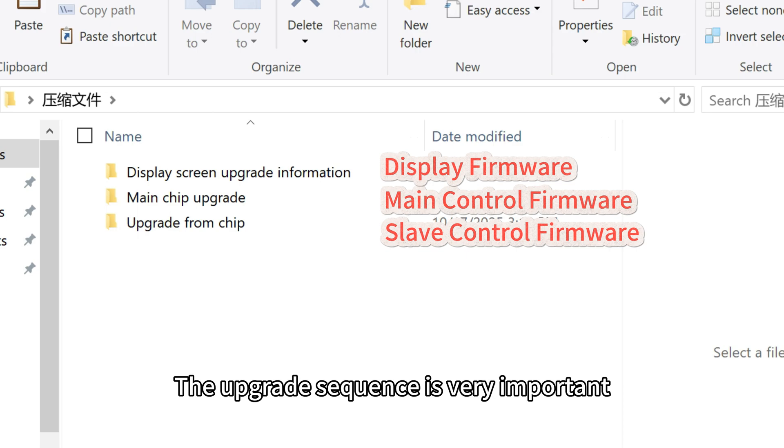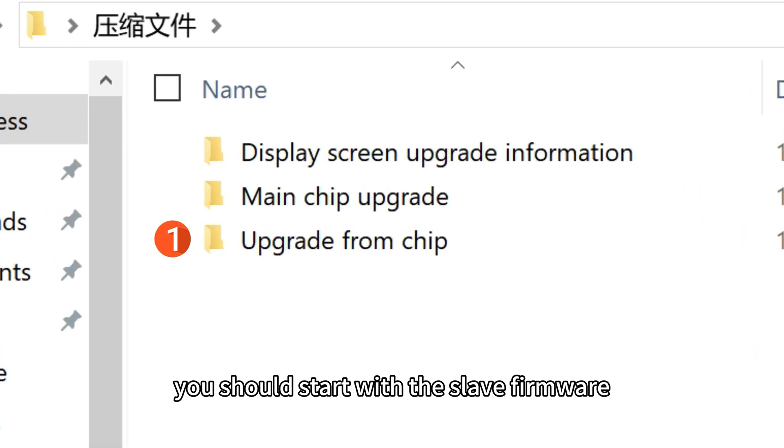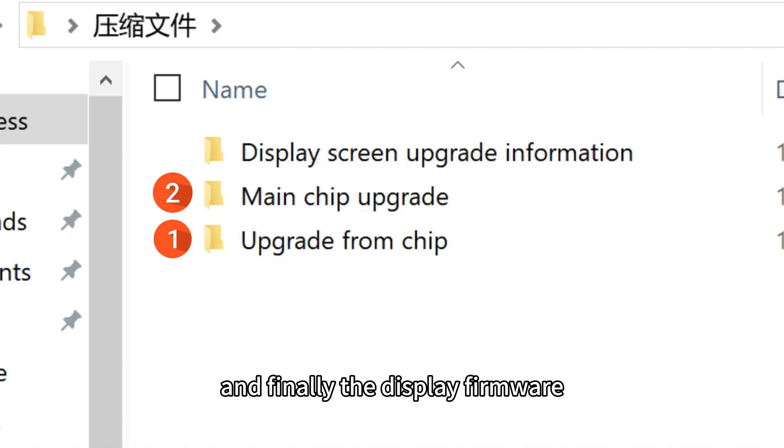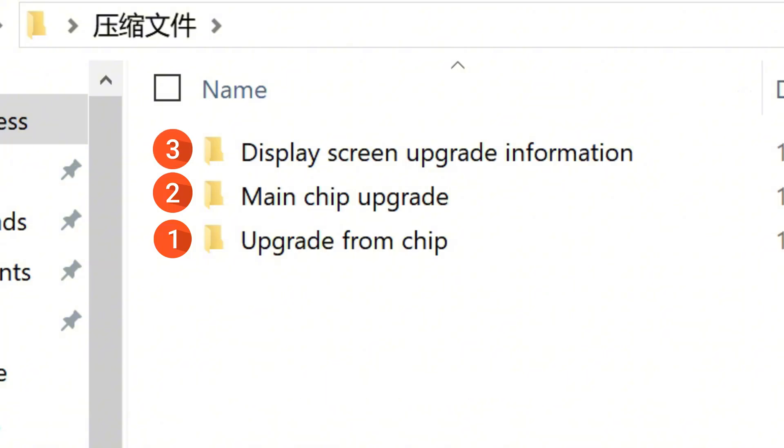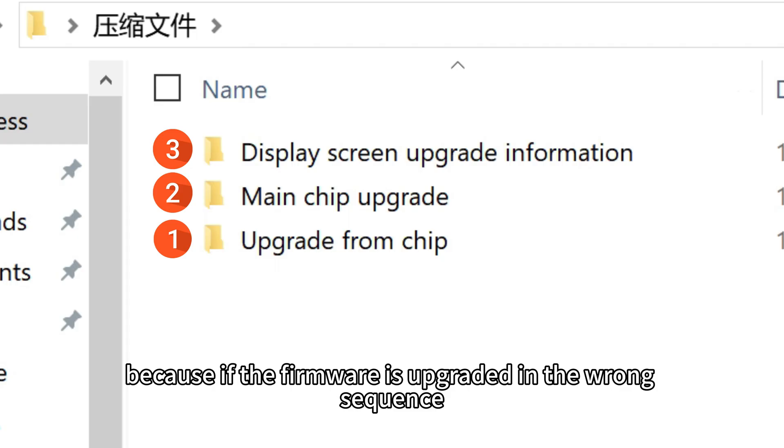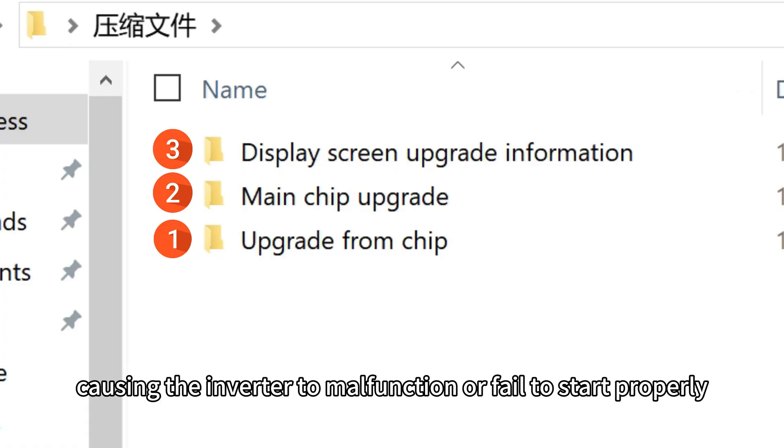The upgrade sequence is very important. You should start with the slave firmware, then upgrade the main firmware, and finally the display firmware. This order must be followed carefully, because if the firmware is upgraded in the wrong sequence, the previous update program may be overwritten or become incompatible, causing the inverter to malfunction or fail to start properly.